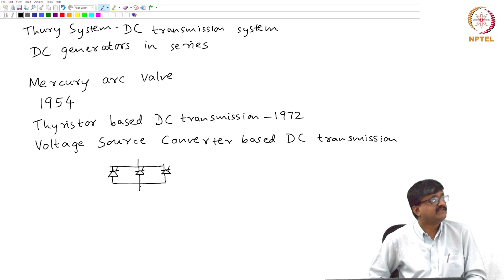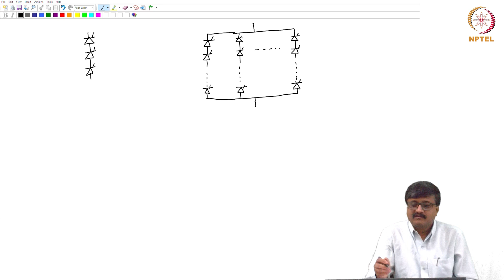Now, if you look at the very first thyristor based DC transmission, neither the current rating nor the voltage rating was available. So at that time, we used both series as well as parallel connection. There were many thyristors connected in series, and many such circuits connected in parallel. This particular circuit, having a large number of thyristors in series and many such series connections in parallel, was given a name: valve. So we use the word valve, or to be more precise, thyristor valve, to mean a large number of thyristors connected in series and such circuits connected in parallel.